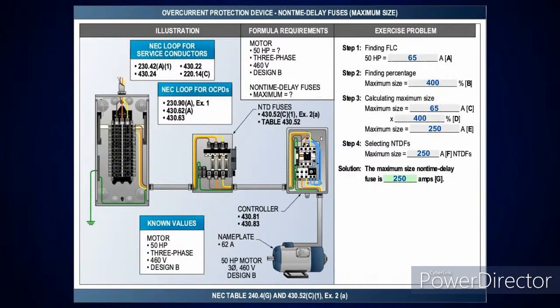Okay? Now, this one, this is your maximum size. All I'm going to be doing is looking right at 430.52(C)(1) and come down. Depending on what cycle you're in, you'd be exception 1 and exception 2, or if you're in 2023, it'd be C1A and B. Okay? So it's the same calculation, same percentages. They just changed it, instead of exception, it's full code text now.